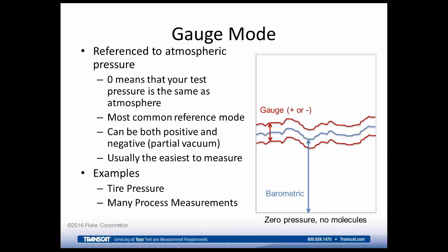So we'll look at gauge mode. Here, everything is referenced to atmospheric pressure. So if you have your dial gauge or pressure transmitter, your pressure measuring device, and you have its test port opened up to atmosphere, just opened up to the air in the room, then it's reading 0, and that means your test pressure is the same as atmosphere. This is probably the most common reference mode, just because it has a lot of usefulness.